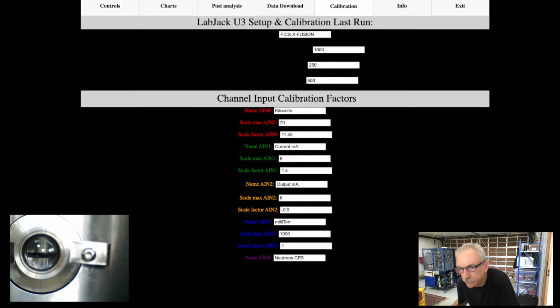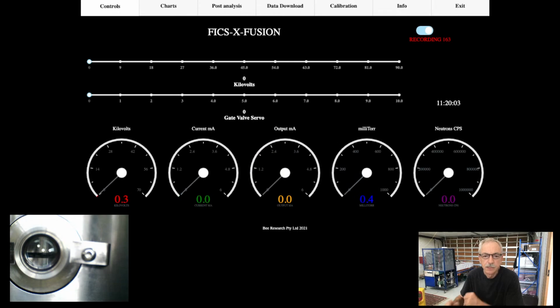and you can see I've set that up here in the calibration, which I can't scroll down. But anyway, one click I believe is 36,000. So when you see these huge neutron numbers, 36,000, it means very little. That's pretty much background radiation when you see that number there. So we're certainly looking for something bigger than that when we start running this detector.